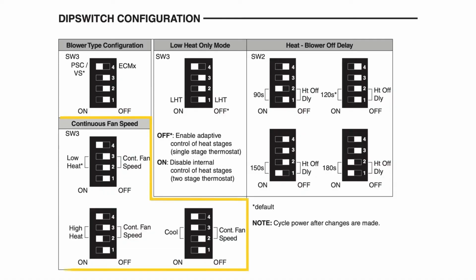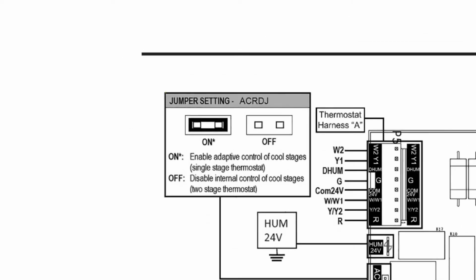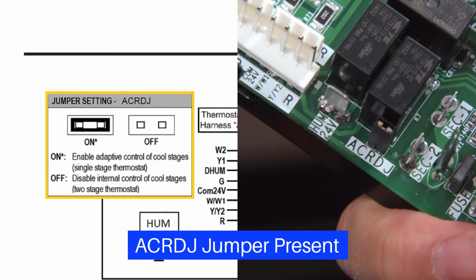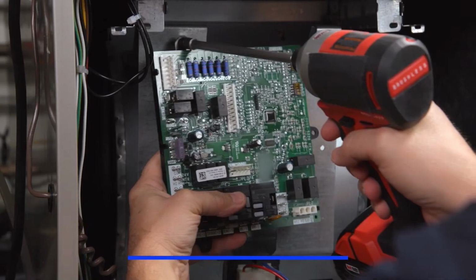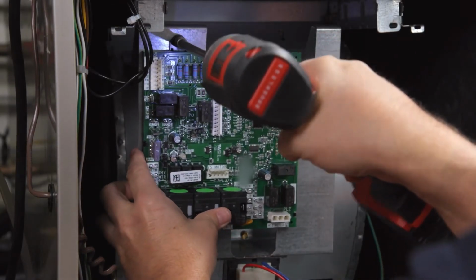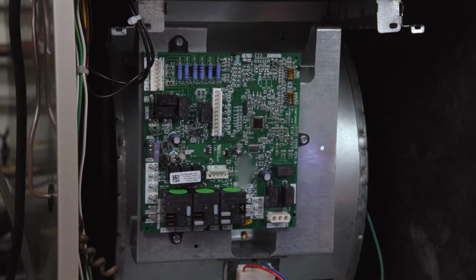This control includes a fan-only speed selection. SW3 dip switch 2 and 3 allow the user to easily select the high heat, low heat, or cool blower speed when the thermostat is set to fan on. For heating applications, this control allows for a single-stage thermostat to be installed and the control to function as a 2-stage control. For cooling applications using a single-stage thermostat with a 2-stage outdoor unit, ensure an air conditioning relay disable jumper is present. The new board matches the existing board's 3-hole mounting system for easy installation.